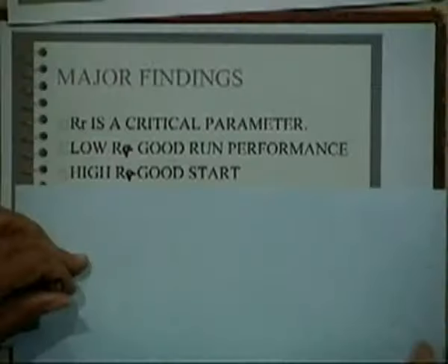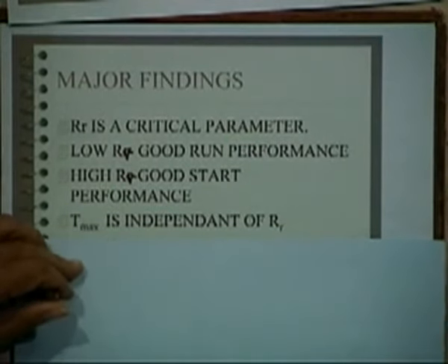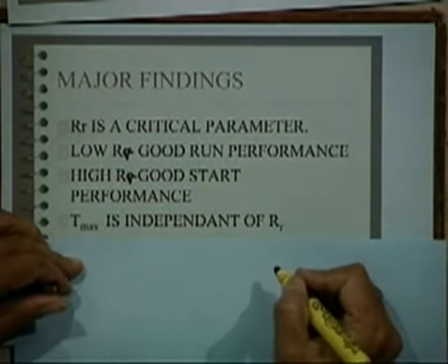Then low rotor resistance gives a good run performance, and high rotor resistance gives a good start performance, right? Then maximum torque is independent of rotor resistance. This is the next conclusion.